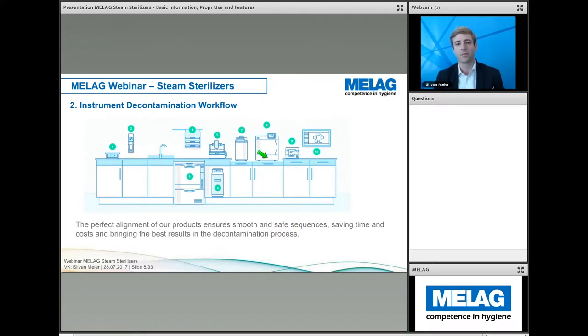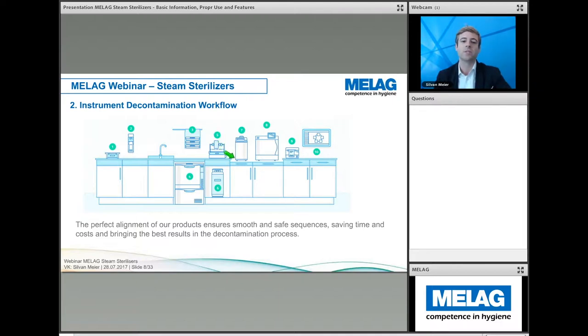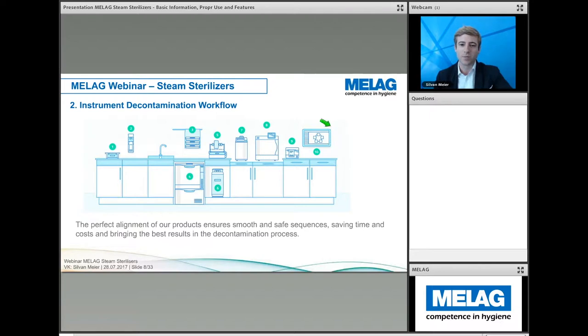Then we move to sterilization. Here we have our flagship sterilizer autoclave, the Vacuklav of the Evolution Series. As a complement, we also have the MelaQuick, which is especially important for small loads of handpieces or instruments that need to be sterilized between patients — it's a high-speed autoclave ensuring safe sterilization. After sterilization, we have the label printer for smooth documentation of batches. The whole process is also monitored with the software MelaTrace for comprehensive documentation.